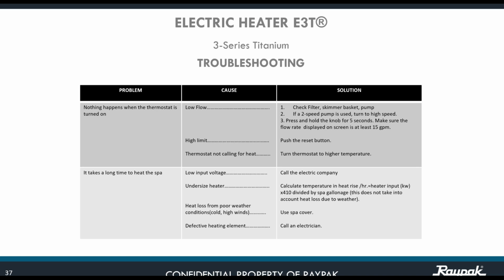If you have a 2-speed pump, make sure that you put it on the high speed. If you want to know, after you put it on high speed, whether you are receiving the proper flow, once again, press and hold the knob for 5 seconds to make sure that the flow rate displayed on the screen is at least 15 gallons per minute. Remember, 50 to 60 gallons per minute is your perfect range for all the units to work properly.